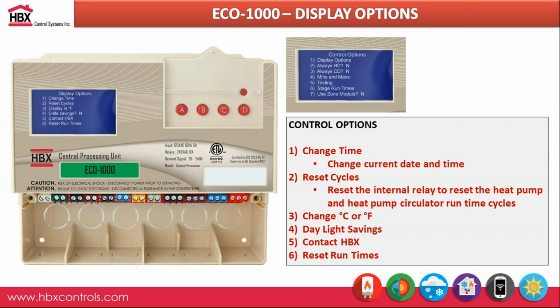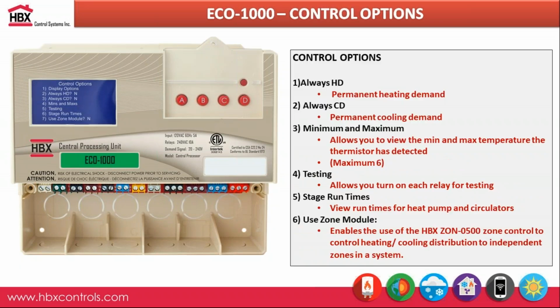You can also use the control options to test relays, just to make sure your pumps and heat pumps are all activating when you first install this. And you can also set the controller to utilize a zone controller. So again, you can only use as an expansion module our zone controller, which is our zone 500. If you want to use that zone 500, you always want to make sure that that is set to yes in the control options, saying that, hey, this expansion module is for zone controller. We're not using this as additional staging or for greater pump control with our other expansion modules.